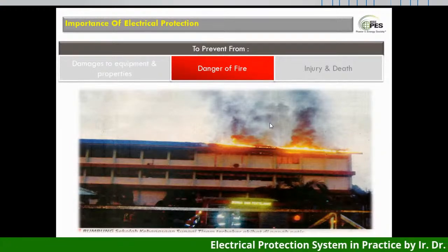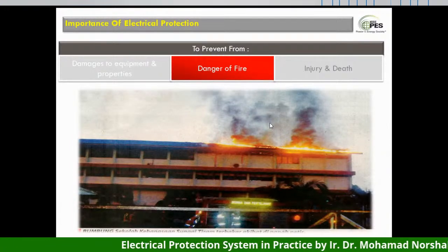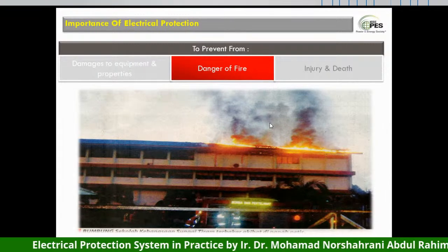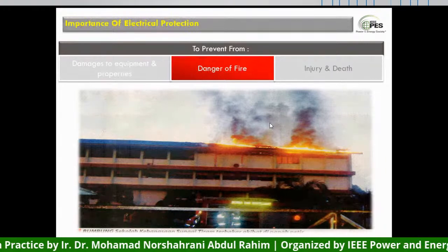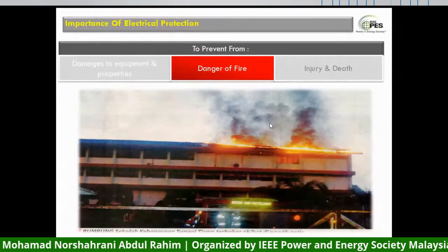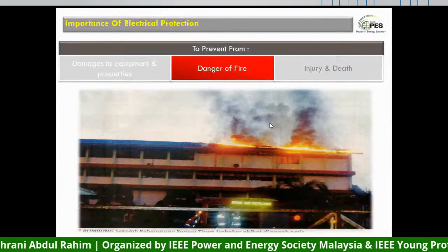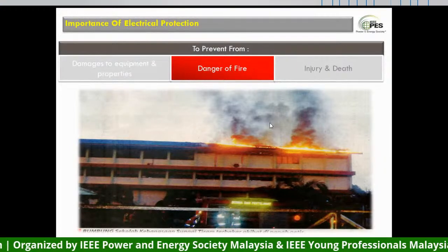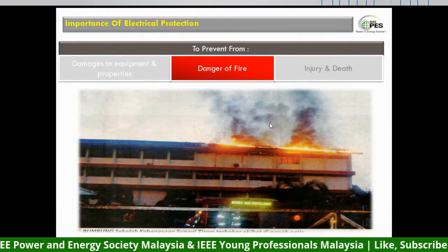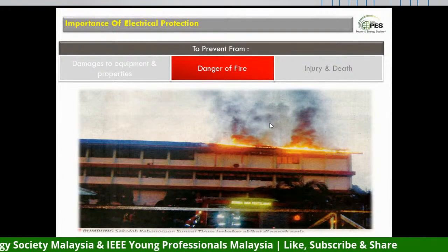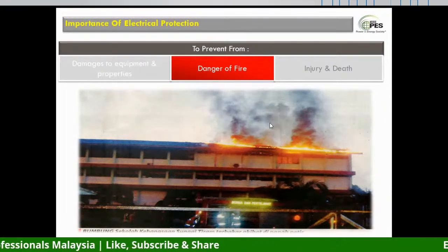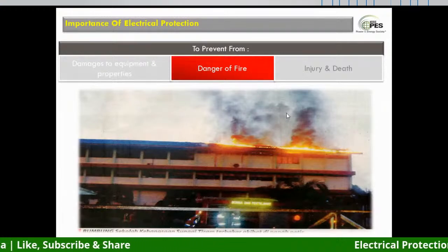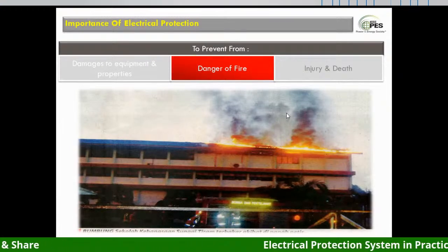For example, in my experience, we proposed to install copper tape as the material for lightning protection. But our client said this area is very prone to copper stealing. So as engineers we need to consider what other types of conductor material can be used to prevent this situation, given the culture in the society.